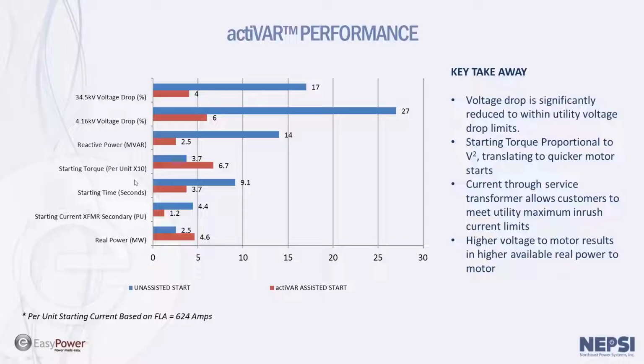This slide here shows the performance of the actiVAR versus across the line start. At the 34.5 kV voltage level, for the across the line start, the voltage drop was 17%. We decreased that to 4%. This was equal to the electric utility's voltage sag limit during motor starting. We've also decreased the secondary voltage drop from 27% down to 6%. This equated to more real power flow to the motor. It went from 2.5 megawatts to 4.6 megawatts, which then equates to more torque for starting. And you can see here that the starting torque, this is times 10, so the starting torque went from 0.37 for across the line to 0.67 for the actiVAR assisted start or capacitor assisted start. Starting time, of course, would go down with the increased torque and increased power flow to the motor.